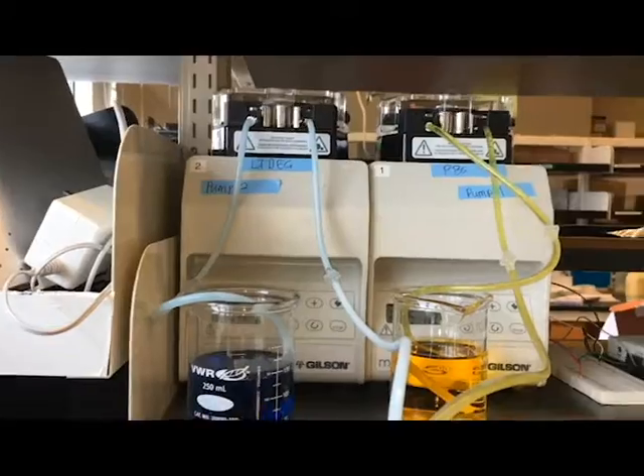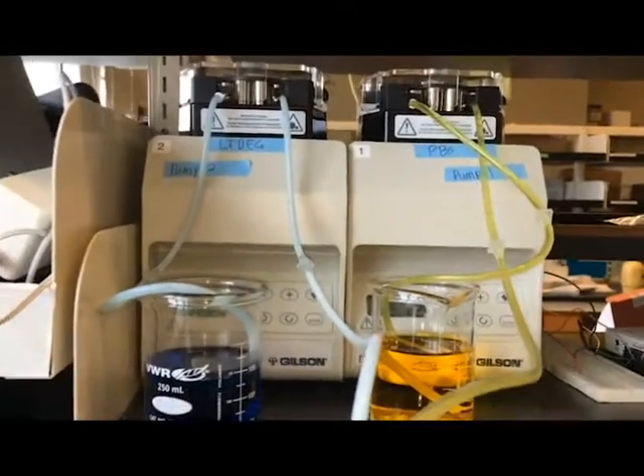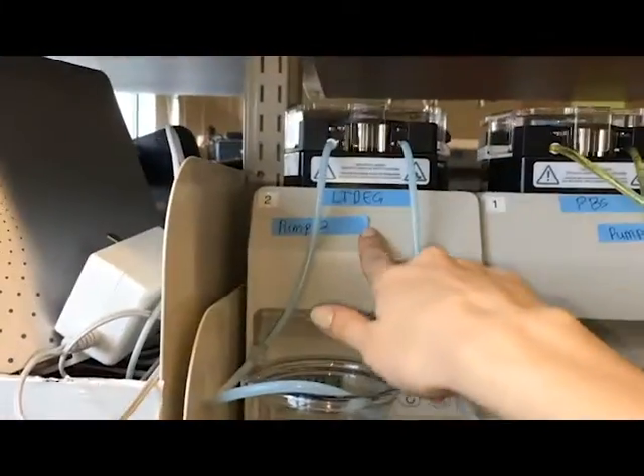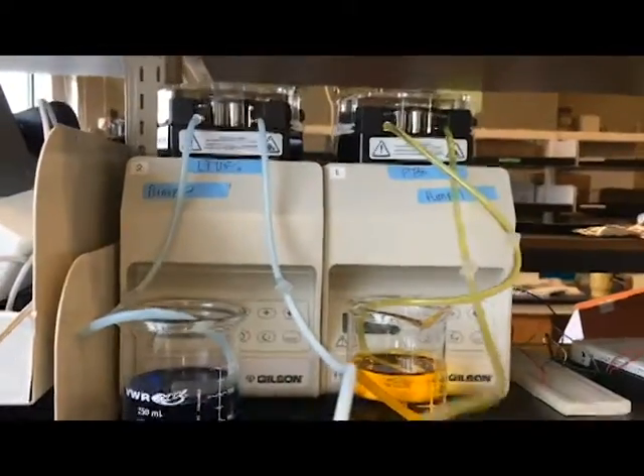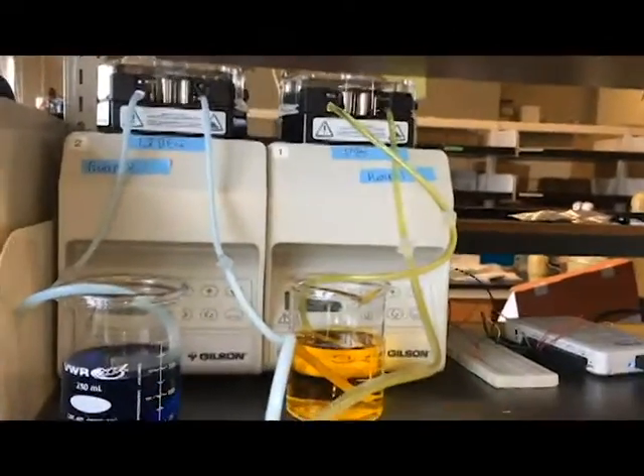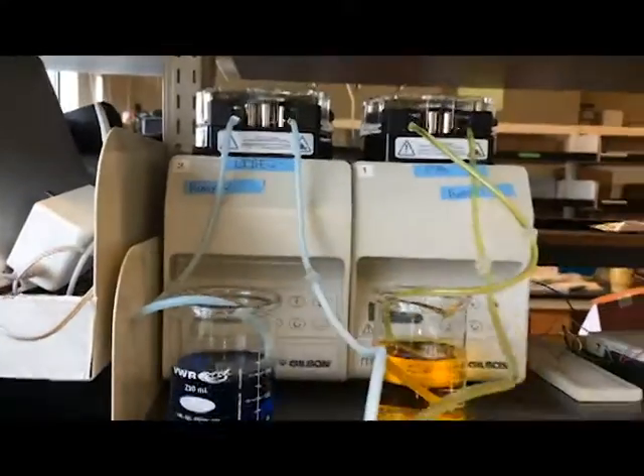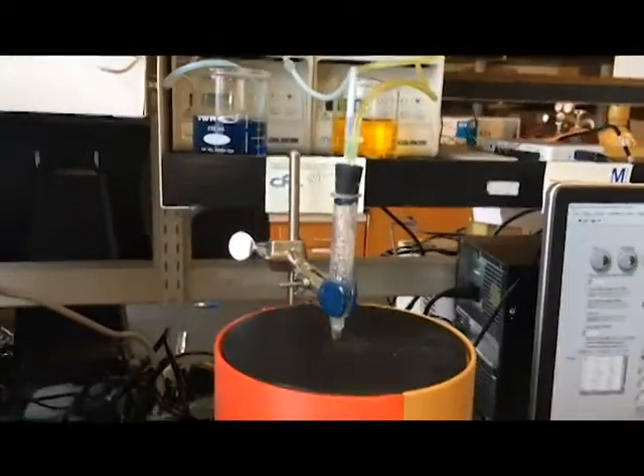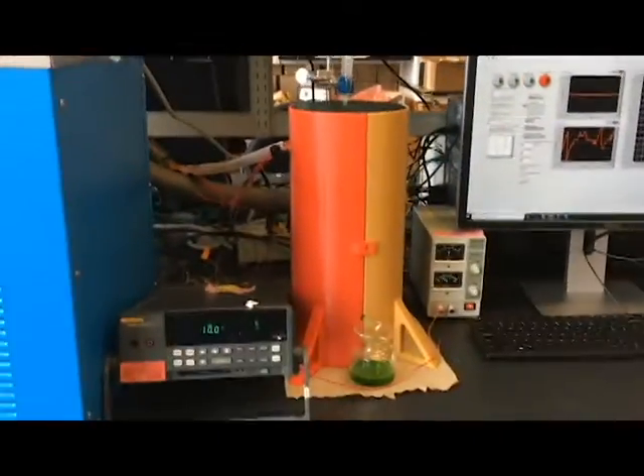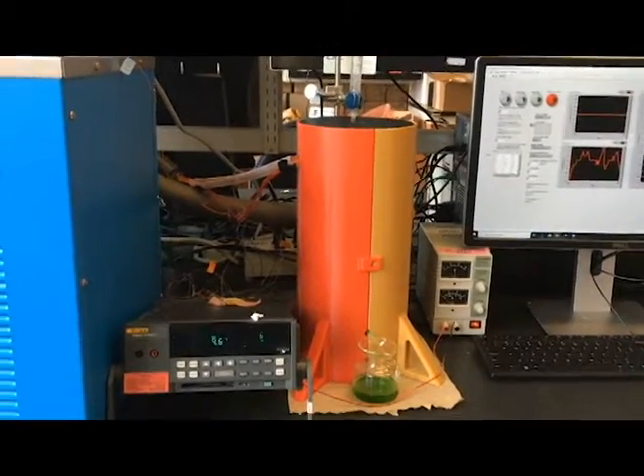Up here we have the 2 peristaltic pumps. For demonstration purposes, we have filled them with water and food coloring, but for the actual experiment they'd be filled with PBS and LT-DEG, and they're used to mix the cryoprotectant agent, which is the LT-DEG, and the buffer solution, which is the PBS, mix them together, feed them through the bubble trap, and then through the housing unit, which houses our heat exchanger and cell chamber.